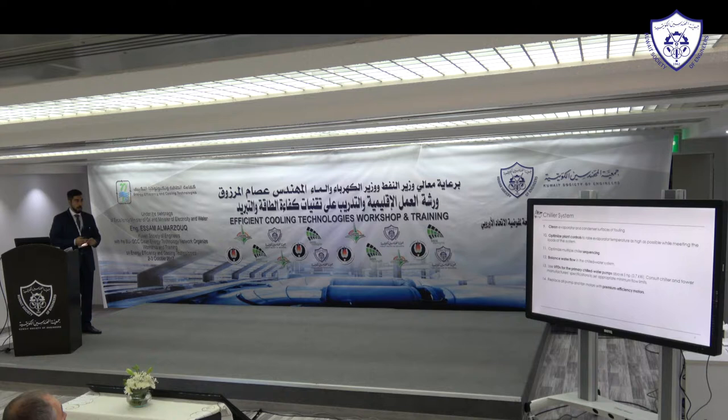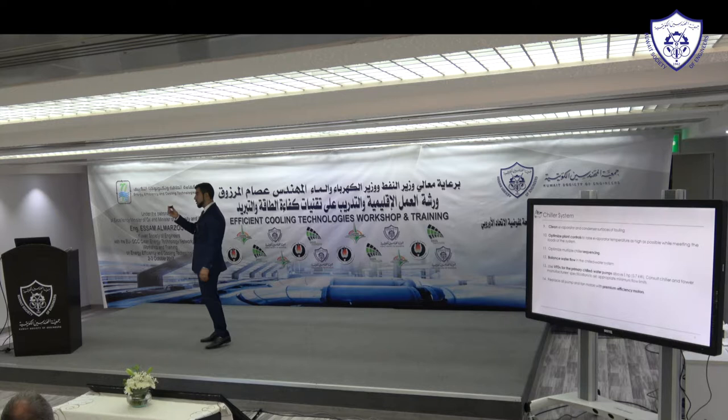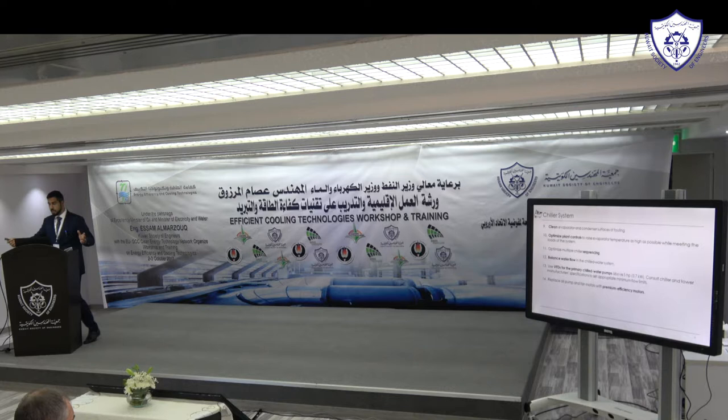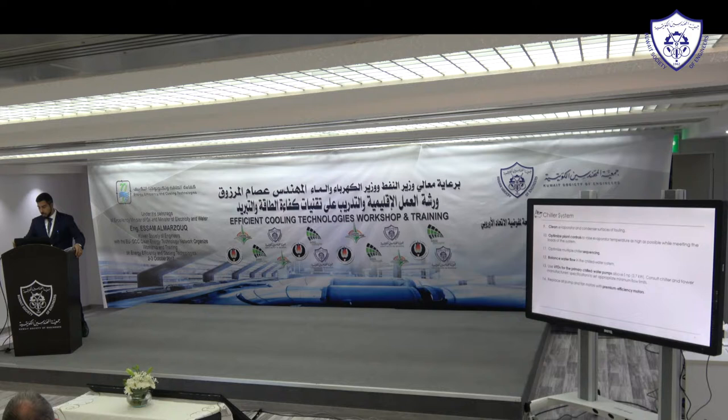For VFDs on primary chilled water pumps in systems without secondary pumps, check with the chiller manufacturer to set appropriate minimum flow limits. For example, if you have 100 liters per second and the manufacturer says minimum is 80, your VFD can reduce from 100 to 80. That's still significant savings because pump power consumption follows the cube law — flow or pump speed at 80% means roughly 50% reduction in power. Even at 80% minimum, it's still a viable solution.